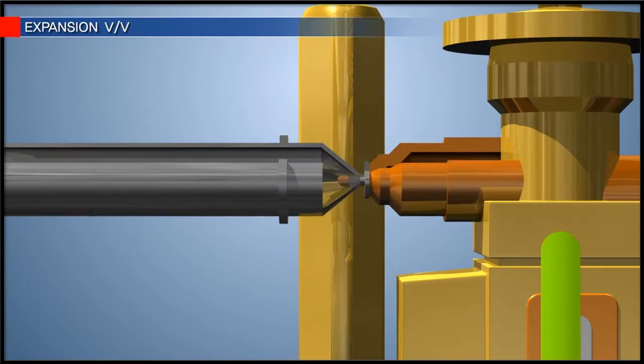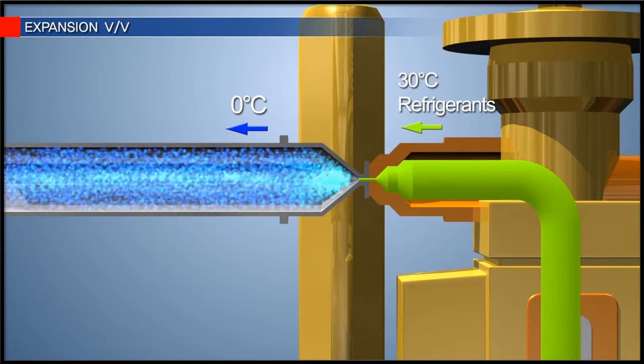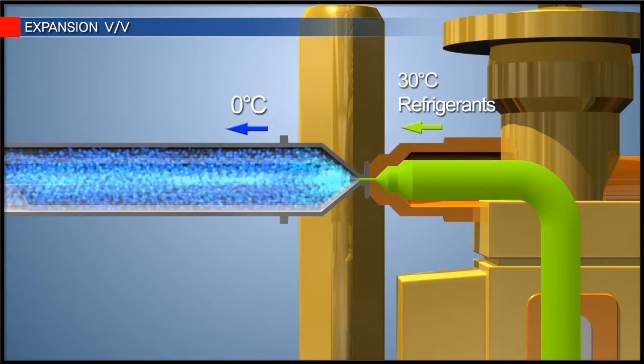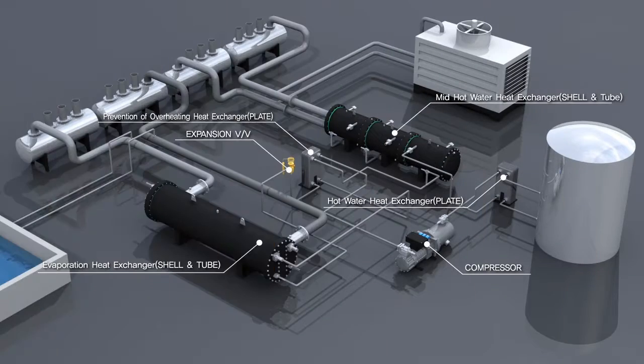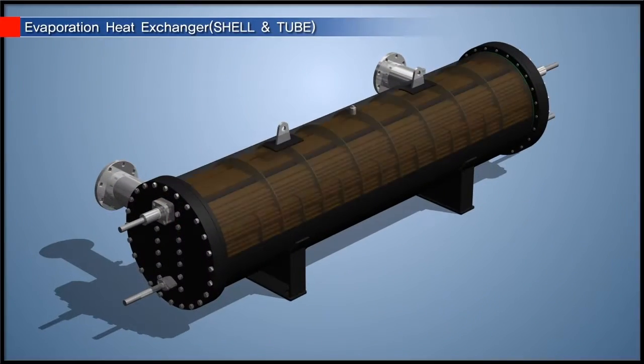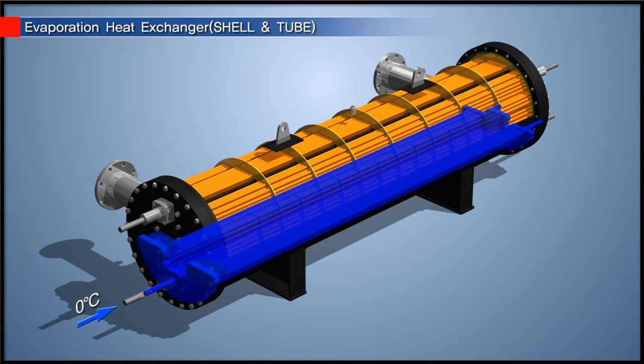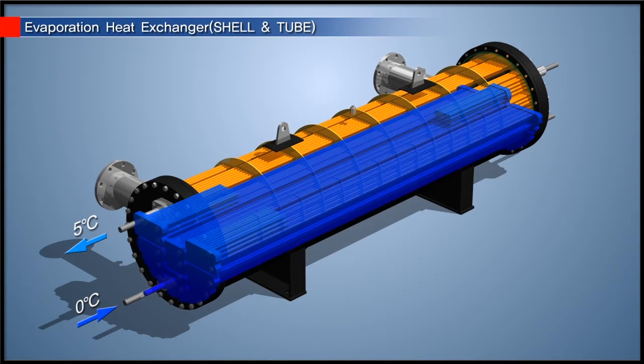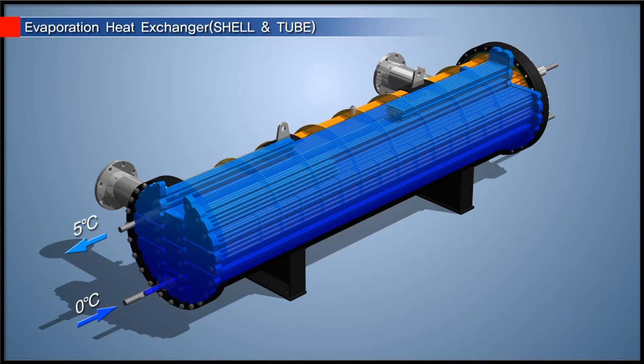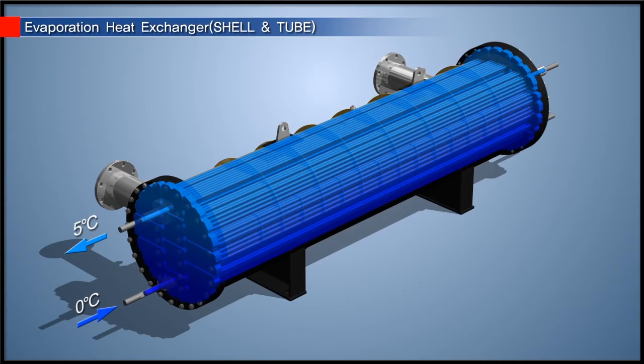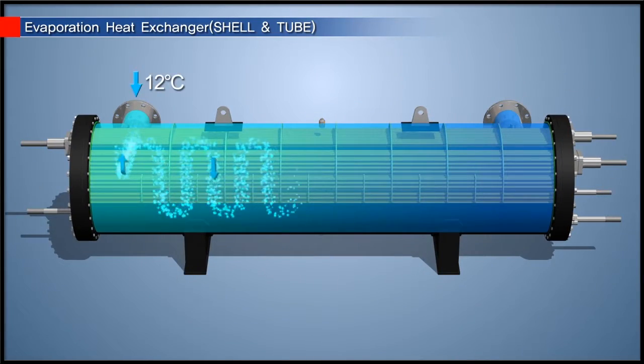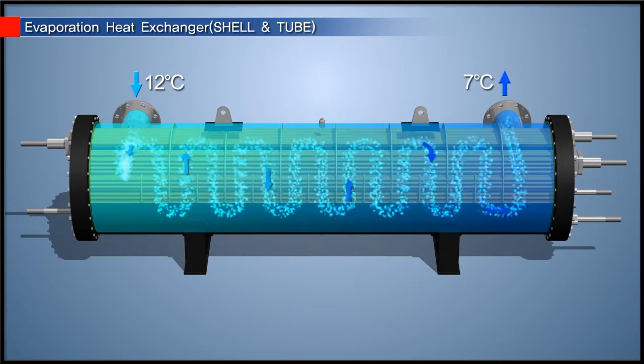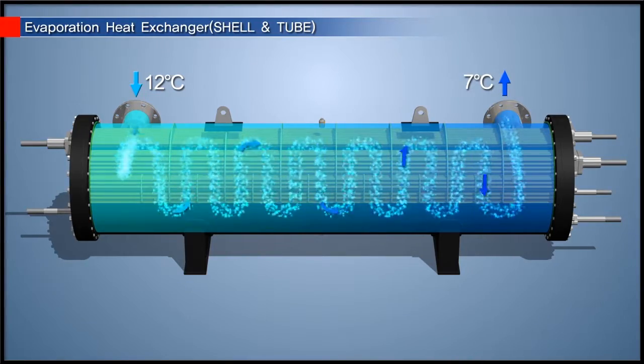Chilled refrigerants at 30 degrees Celsius become 0 degrees Celsius refrigerants through the expansion valve. Evaporated refrigerants at 0 degrees Celsius go through the shell and tube type evaporation heat exchanger, and lower the temperature of chilled water, which has a cooling load, from 12 degrees Celsius to 7 degrees Celsius.